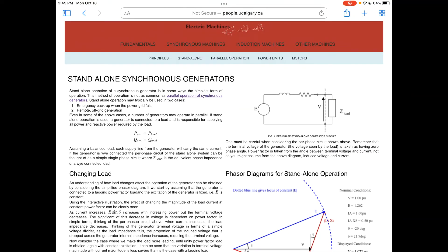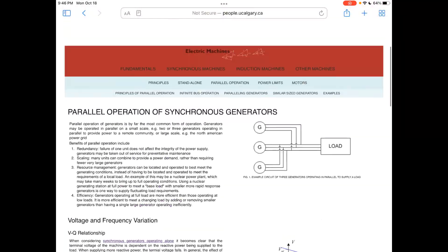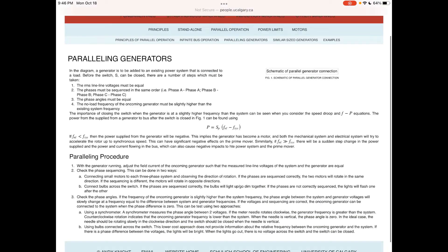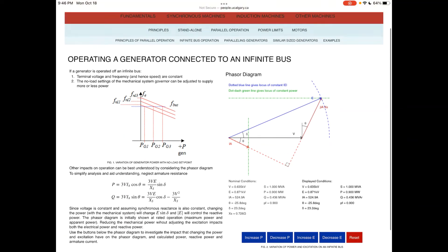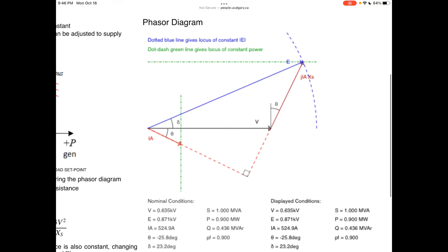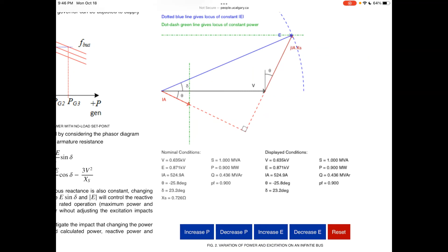Now let's look at the parallel operation with the infinite bus. When a generator is connected to the grid, the terminal voltage is kept constant. The network is more powerful than you, so your terminal voltage will be held constant at the system voltage — the rated voltage of the whole system — whatever you try to change.